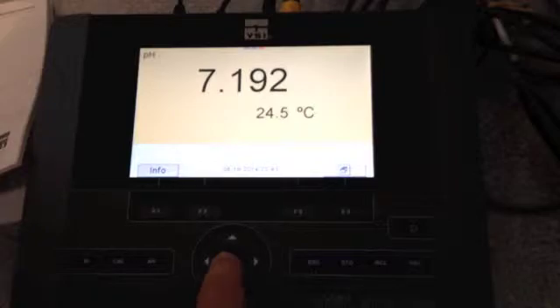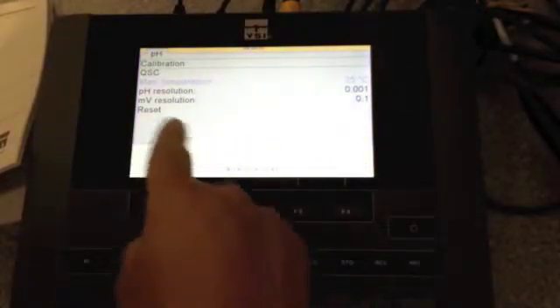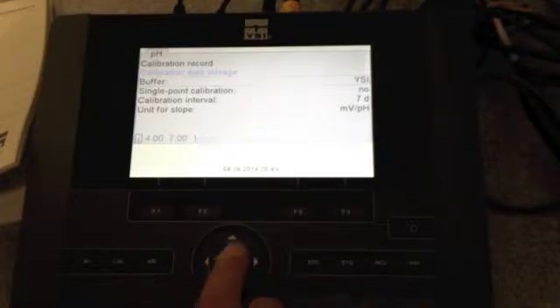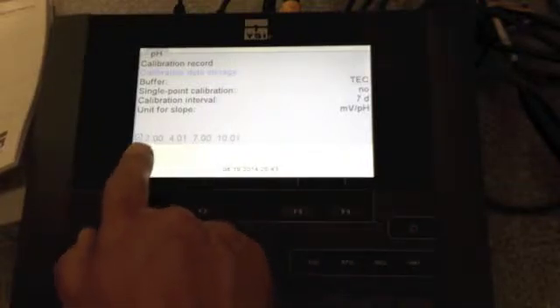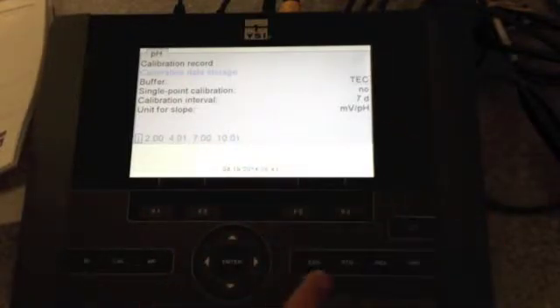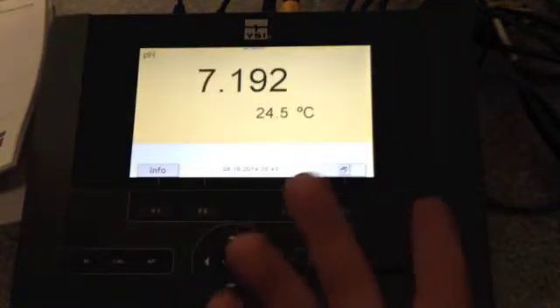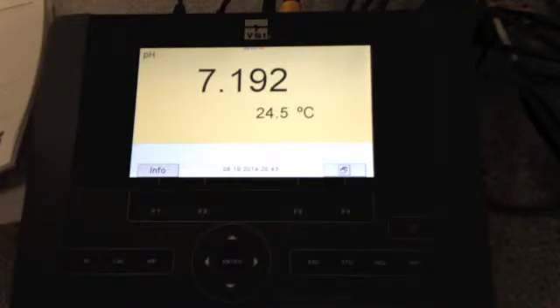When you're in the pH mode, just hit the enter button in the center, and you're going to see calibration highlighted. Hit enter again, and just go down till it says buffer, and once that's highlighted, you can hit the enter button, and then you can use your arrows to change. For example, if you wanted to do technical buffers, on the bottom of the screen you will see what those technical buffers include: 4.01, 7, 10.01. So that's important to understand, and once you're done there, you can just hit escape, and you are now at a point where you're using the technical buffers.